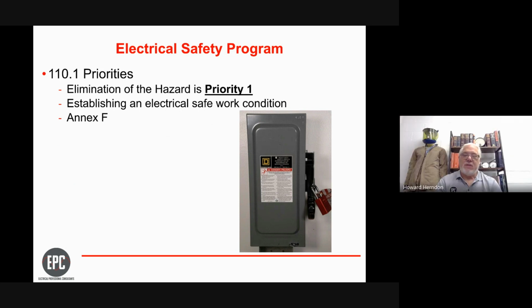I have people tell me all the time, we won't get a Nevada Energy outage because of the hassle it takes, we'll just shut the main off. Well, what keeps someone from hitting, touching, or being exposed to the line side of that main circuit breaker? If there are barriers in the equipment, we can probably safely do that, and this goes back to knowing the equipment. But that takes a real risk assessment to figure out.